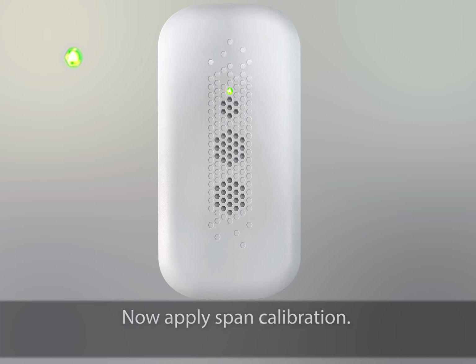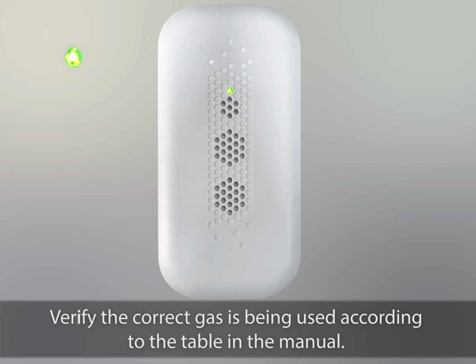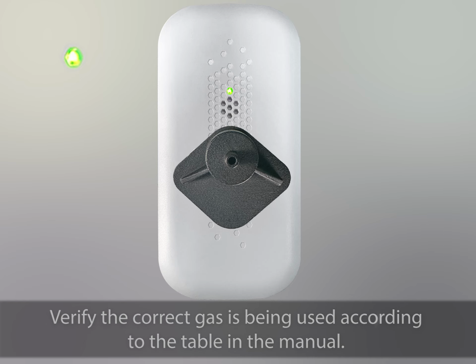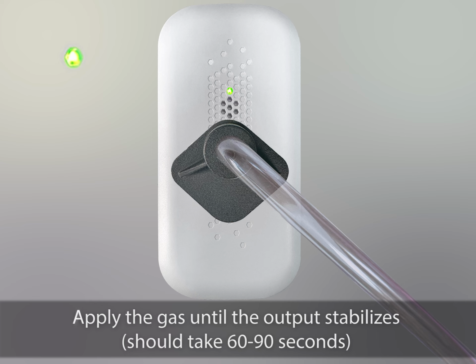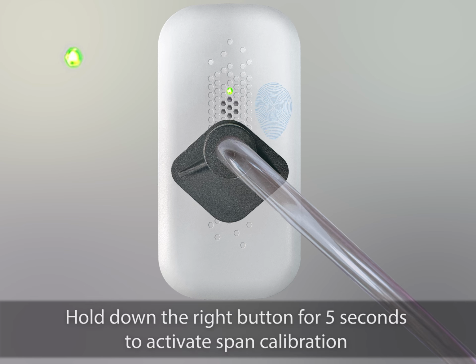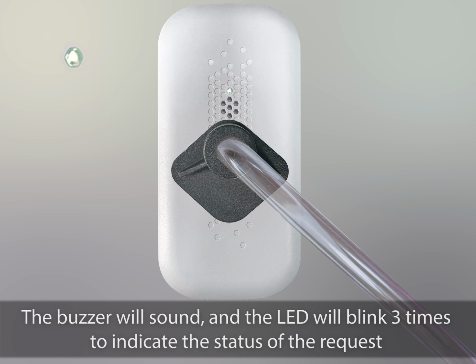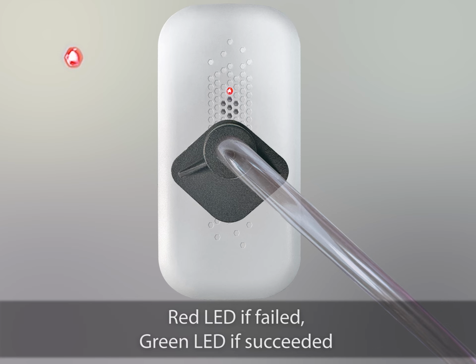Next, apply span calibration. Verify the correct gas is being used according to the table in the manual. Apply the gas until the output stabilizes. This should take 60 to 90 seconds. Hold down the right touch zone for 5 seconds to activate span calibration. The buzzer will sound and the LED will blink 3 times to indicate the status of the request. Red LED equals failed, green LED equals succeeded.